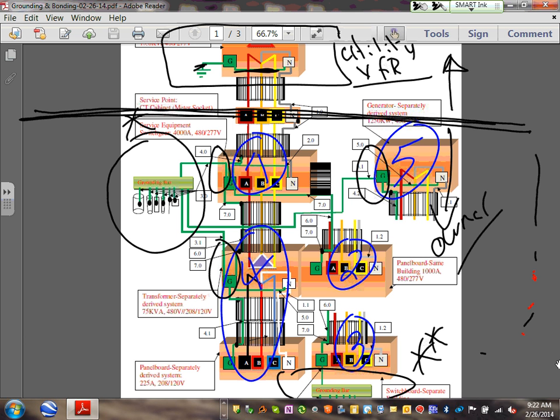So the main reason for grounding and bonding is the safety of the people and the equipment, and not burning buildings. We don't burn electrical equipment, we don't burn buildings, and we facilitate the operation of the overcurrent protection devices and the proper operation of the power system. When you have a neutral bonded and grounded, the power system will work efficiently, work properly, and work safely. Any comments, any questions?